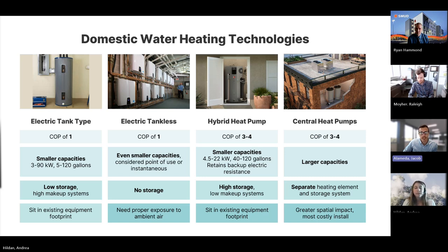If your demand is larger than that and you want a more efficient system, you can go with a hybrid heat pump. The hybrid heat pump pulls heat out of the air and puts it into your domestic hot water. It also has an electric resistance that can be used as the backup for that. One of the benefits of going with a heat pump like this is that you can get some, quote unquote, free cooling for your building. So say you put this unit in a mechanical room with a bunch of pumps and air compressors and other equipment that lets off a bunch of heat. This type of water heater can cool that space for you while making your hot water.